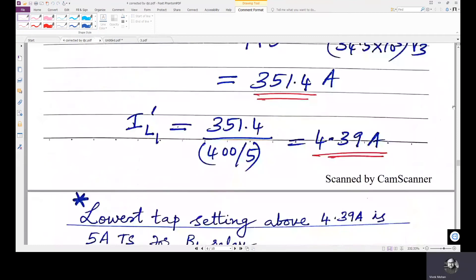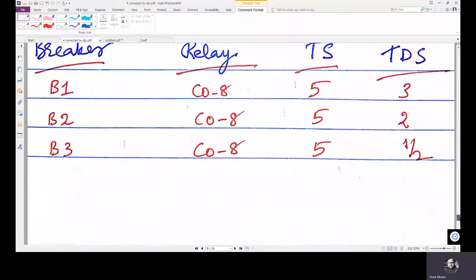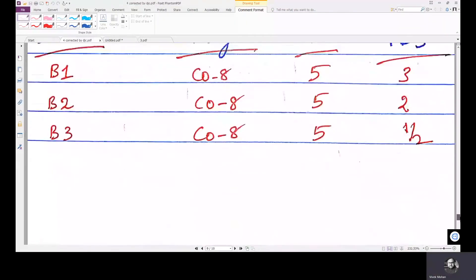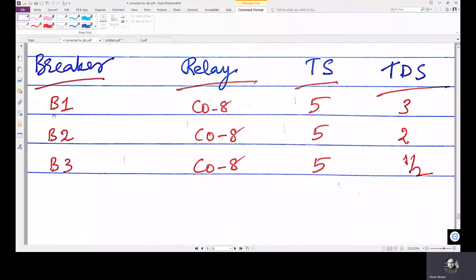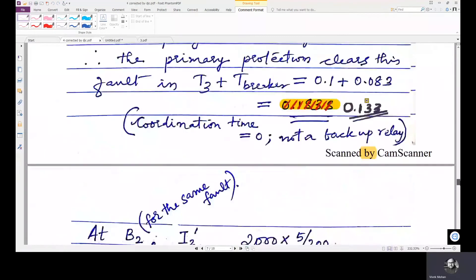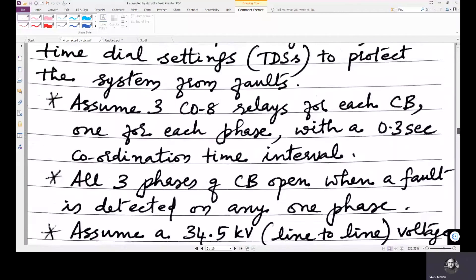So for all the breakers: B3 has a 5 ampere tap setting, B2 has a 5 ampere tap setting, and B1 has a 5 ampere tap setting. That completes the first part of the problem — selecting the current tap settings. Now we are going to find the time dial settings for the same problem.